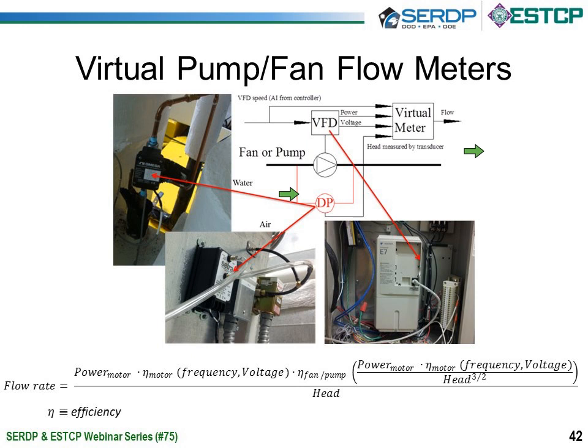And actually what we input is the head produced by the pump or the fan. Combining those into a flow rate equation that again is fit using training data to the actual device, we can then determine, and this is used to model the motor efficiency and the fan pump efficiency as a function of conditions. We then have an equation once we're done training for flow rate as a function of the variables coming into the virtual flow meter. So that for any measured conditions that we get primarily from the DP and the VFD, we're able to determine a virtual value for the flow rate.